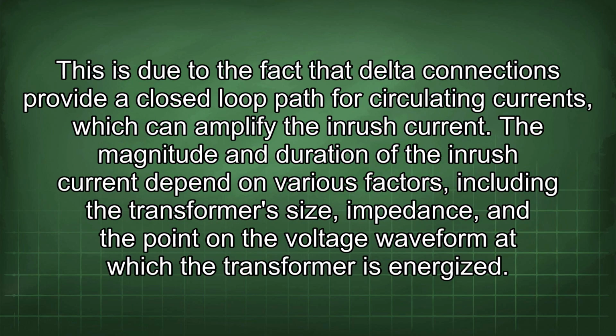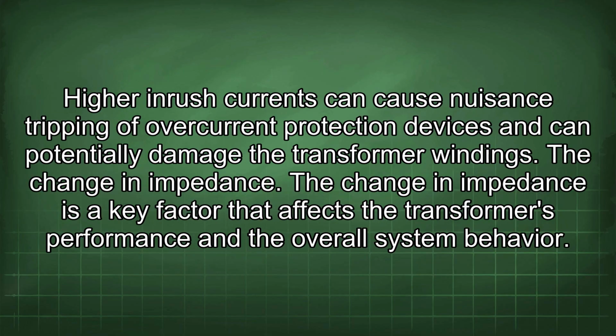This is due to the fact that delta connections provide a closed-loop path for circulating currents, which can amplify the inrush current. The magnitude and duration of the inrush current depend on various factors, including the transformer's size, impedance, and the point on the voltage waveform at which the transformer is energized. Higher inrush currents can cause nuisance tripping of overcurrent protection devices and can potentially damage the transformer windings.